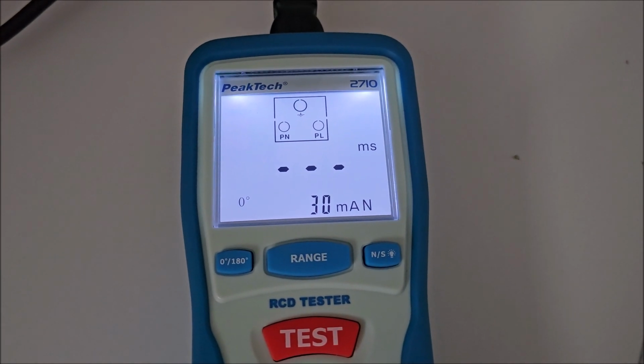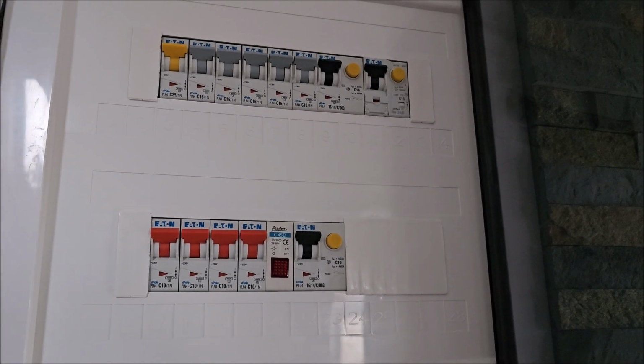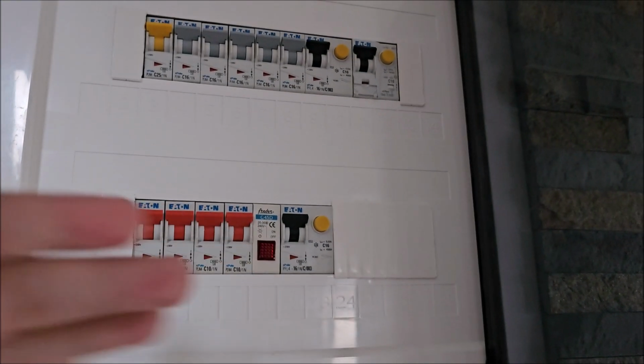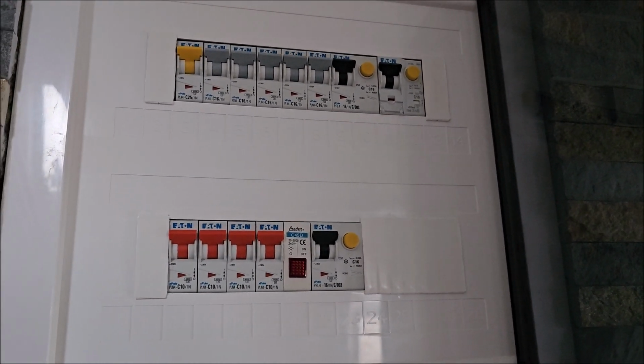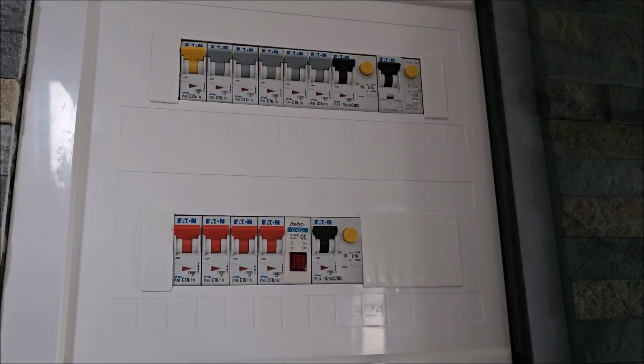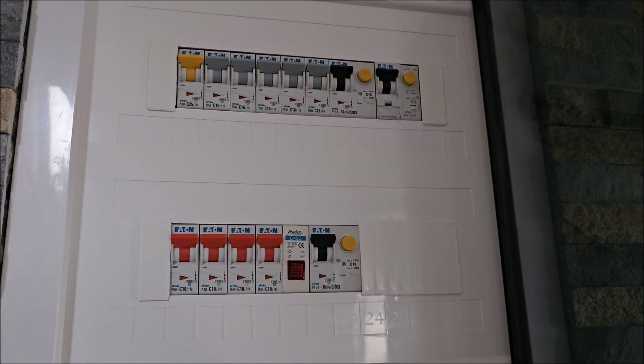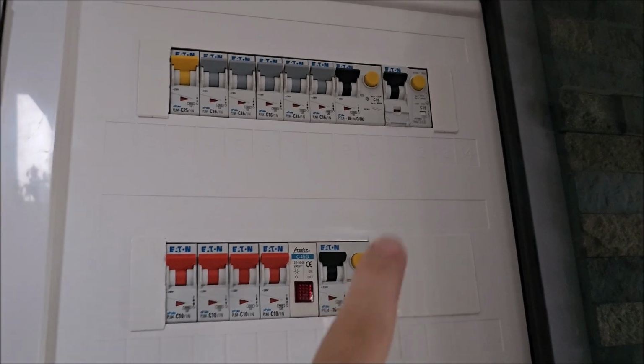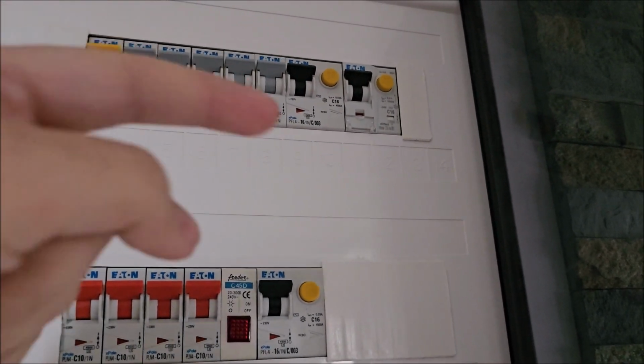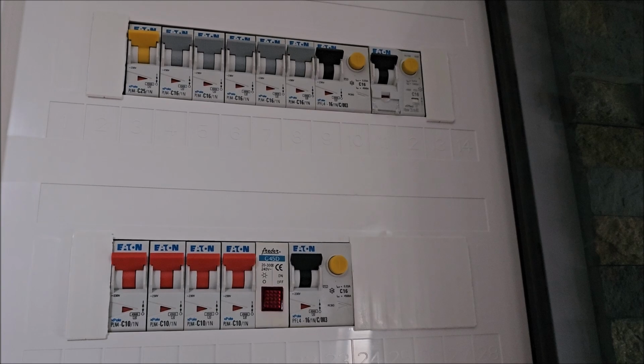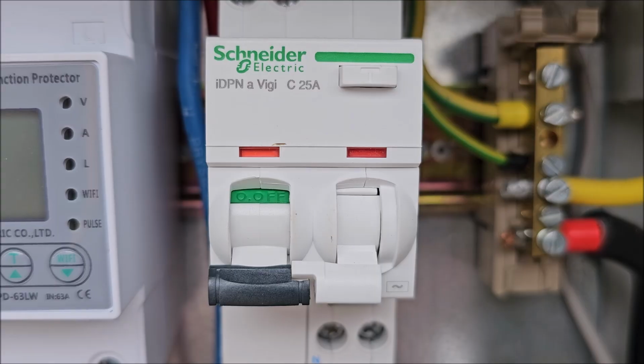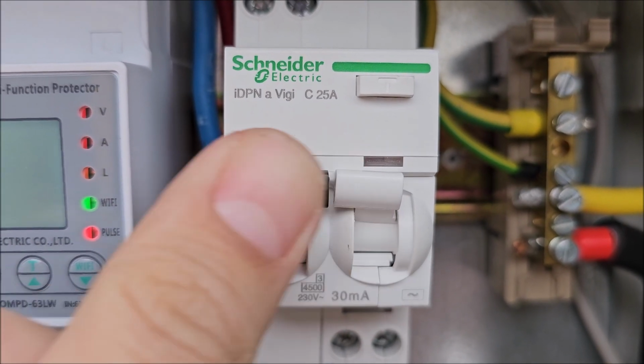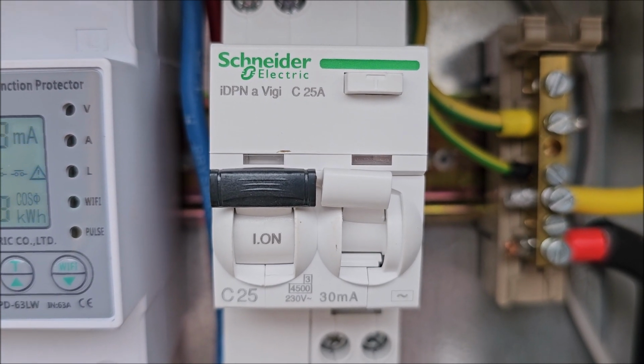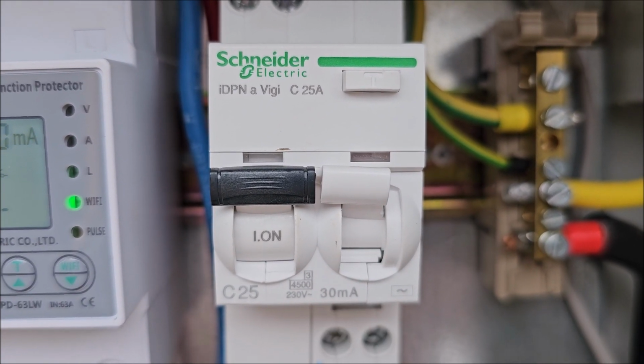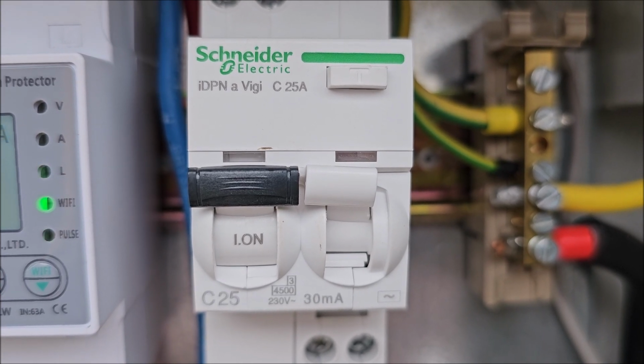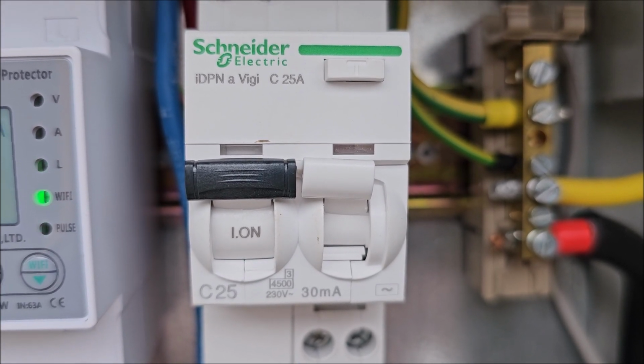If there was any question about it, this one obviously did not trip, while this one did, because the other has a much quicker reaction time. So this has a lower tripping current but a higher reaction time. I'm extremely surprised that Eaton, and also Schneider, the manufacturer of the outside one, did not tell me this. This is the outside one, clearly tripped, and this is its value. Weirdly enough, they didn't know it has a completely different tripping time.